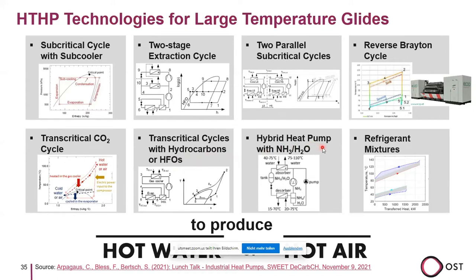Then hybrid heat pump with ammonia water system using absorption and desorption. So the ammonia is in a gas form and compressed to the higher pressure, and the water will be pumped up to the higher pressure. Then they join again and absorb each other, let's say, and release the heat to the process.